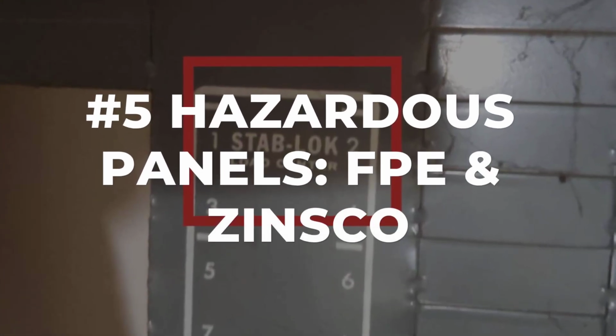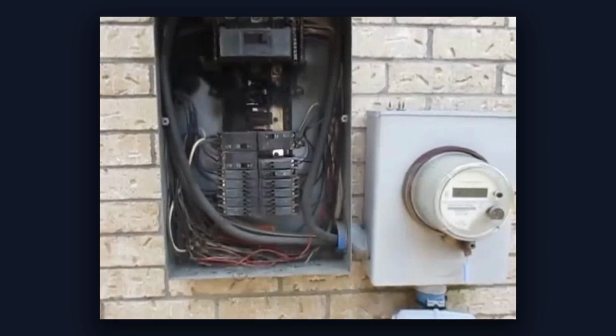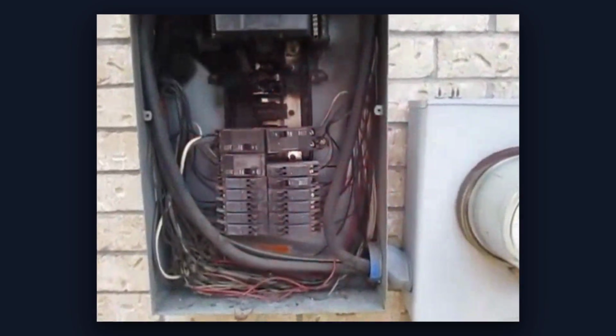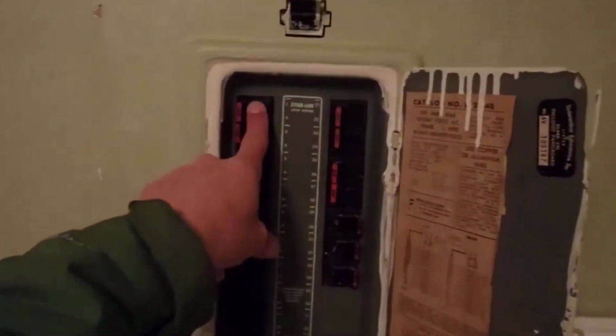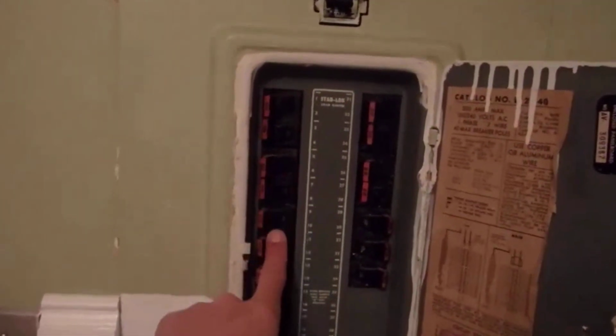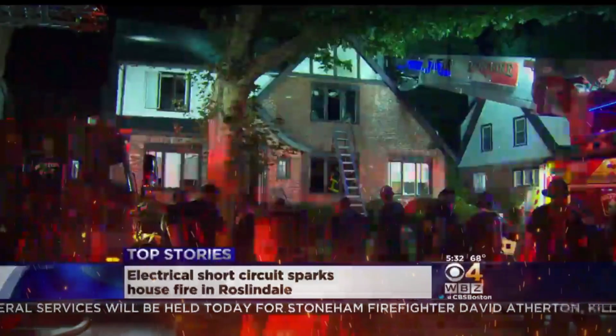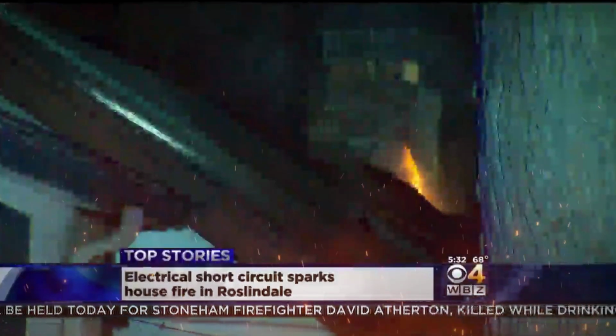Number 5, hazardous electrical panels, specifically Federal Pacific Stab-Lok and Zinsco, pose a risk that goes far beyond outdated wiring. These panels are notorious for circuit breakers that fail to trip during overloads, turning a minor fault into a potential house fire.